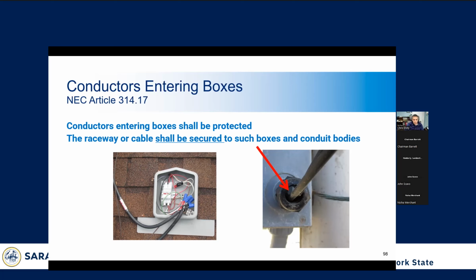And then on the left, the flashing is good. You can see it goes up underneath the shingles. It's rated for outdoor use. However, the contractor, instead of running the wires through a knockout, they just ran it up underneath the cover of the enclosure, which basically leaves it wide open for rain and anything else to get in. They would need to disconnect this and run it through the knockouts to ensure that it's installed properly. And also, this red one and possibly the blue wire nuts are not rated for outdoor use. And even though this is like an enclosed space, it's still installed outdoors. It's going to have the humidity and the temperature of the outdoor environment. So all the equipment has to be rated for outdoor use.